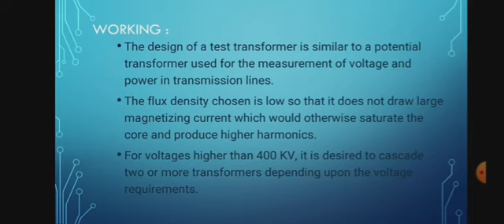Most of the present day transmission and distribution networks are operating on AC voltages and hence most of the testing equipment relates to high AC voltages. Even though most of the equipment on the system is 3-phase, a single phase transformer operating at power frequency is the most common for HVAC testing equipment. Test transformers normally used for the purpose have low power rating but high voltage ratings. These transformers are mainly used for short time tests on high voltage equipment.